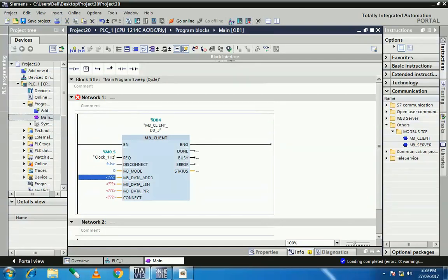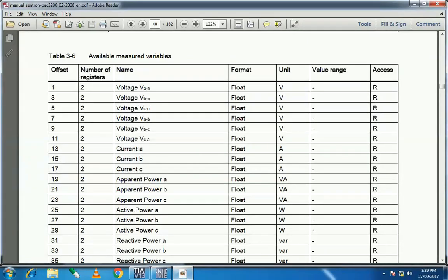Next is MB_DATA_ADDR, the Modbus data address. We will read three different variables — I'll show you in the manual. First is the voltage between the first phase and neutral, second is the voltage between the second phase and neutral, and third is the voltage between the third phase and neutral. The data type for each variable is float, and each variable uses two registers, meaning two words.